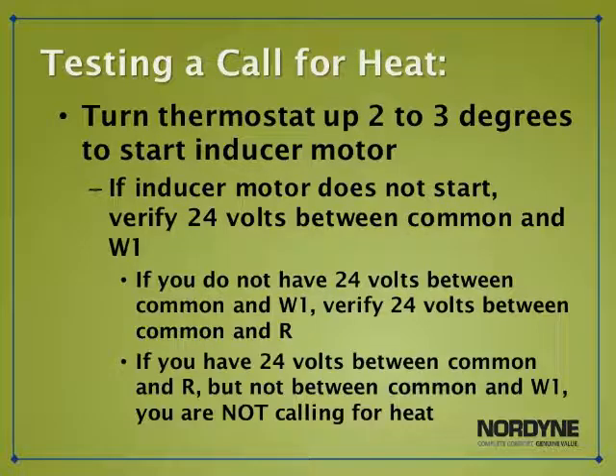If you have 24 volt AC between common and R, but not between common and W, that means we are not calling for heat at the interface control board. The problem could be either in your low voltage wiring or in the thermostat itself. Many times, weak batteries in the thermostat will cause the thermostat to not make a call for heat. It's very common to find this problem related to weak batteries.